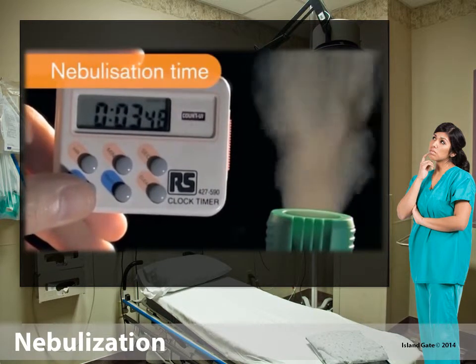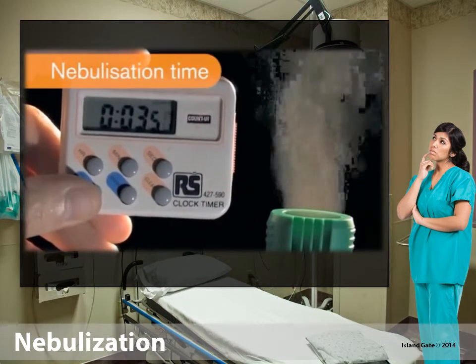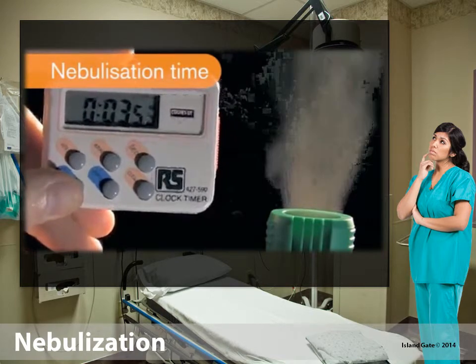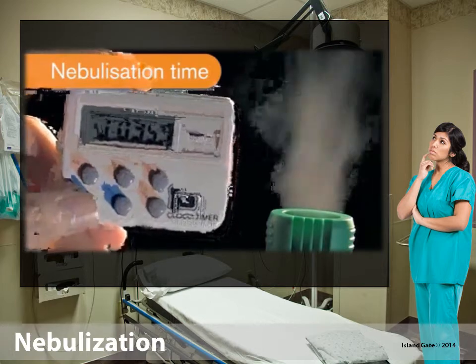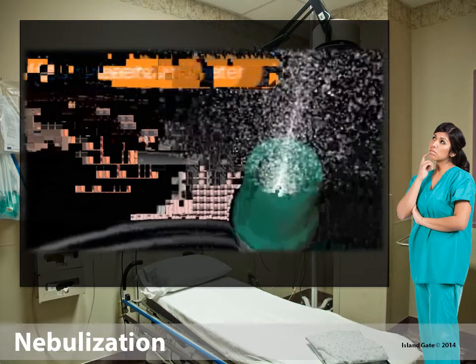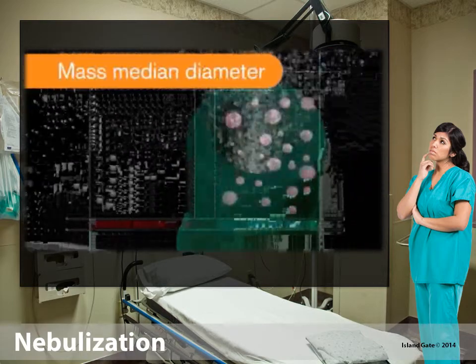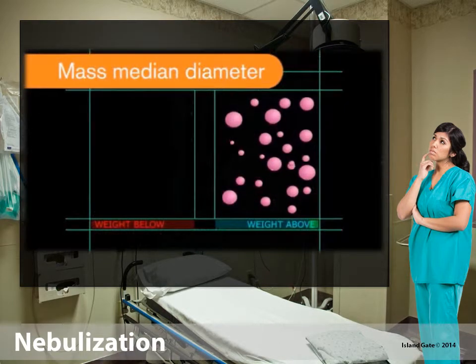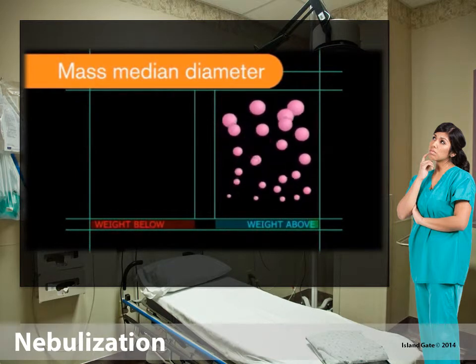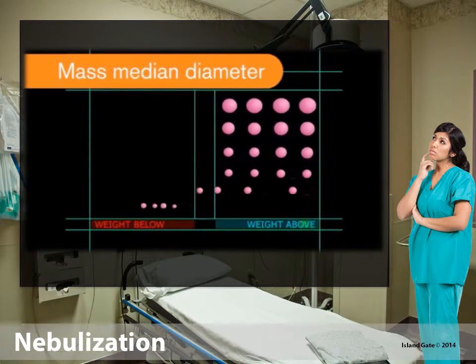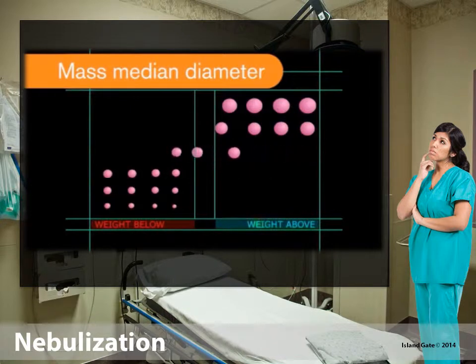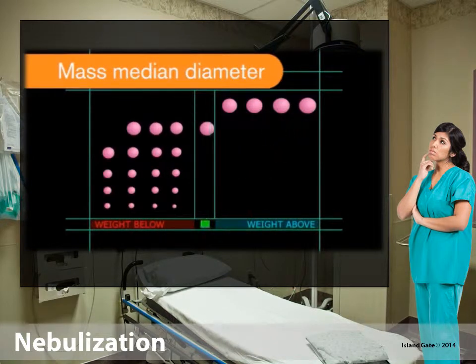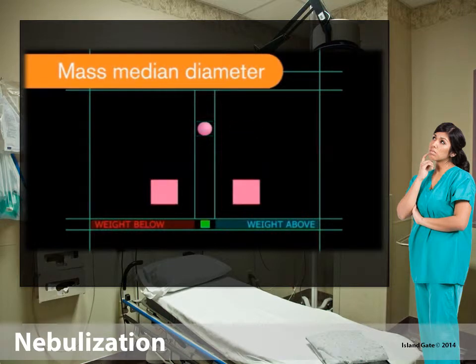The nebulization time is measured from the start of nebulization until the cessation of continuous nebulization, or until the nebulizer starts to splutter. Probably the most simple and useful single measure of droplet size is the mass median diameter, usually abbreviated to mmD. This is defined as half of the mass of nebulized aerosol is contained in droplets which are larger than the mmD and half smaller.